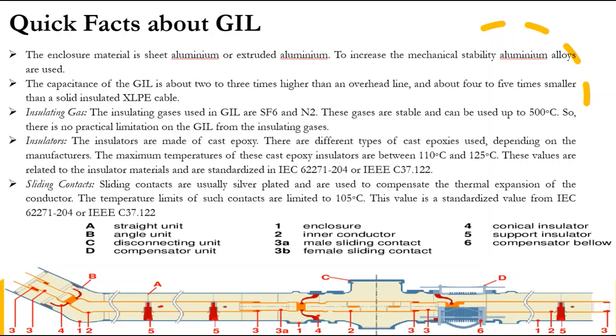The insulators are made of cast epoxy. There are different types of cast epoxies used depending on the manufacturer. The maximum temperatures of these cast epoxy insulators are between 110 and 125 degrees Celsius. These values are standardized in IEC 62271-204 or IEEE C37.122. Sliding contacts are usually silver plated and are used to compensate the thermal expansion of the conductor. The temperature limits of such contacts are limited to 105 degrees Celsius, also standardized in IEC 62271-204 or IEEE C37.122.